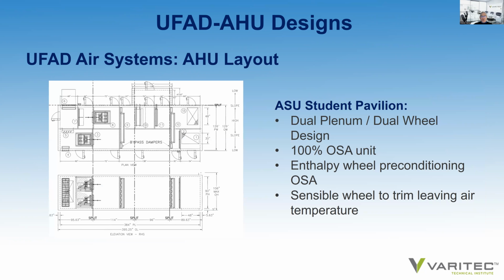There's another solution that uses a dual tunnel design where you have an enthalpy wheel and a sensible heat transfer wheel. The enthalpy wheel preconditions the outside air, so you have enhanced energy efficiency. And the sensible unit actually uses the thermal energy off the return air to post-heat the supply air off the coil. This solution does offer better temperature control to maintain a properly dehumidified 63-degree supply air solution. However, you do have a static pressure gain through the secondary wheel, the sensible heat recovery wheel.